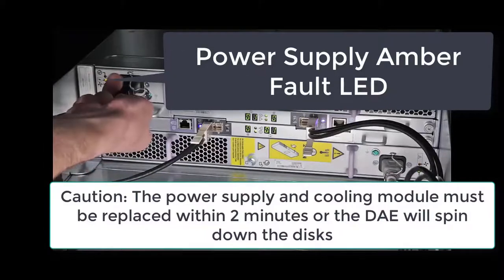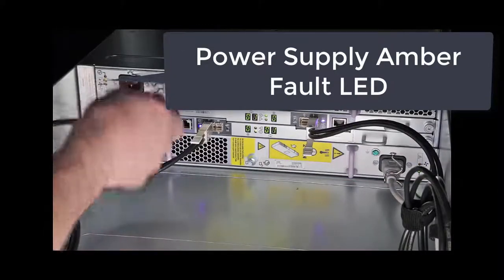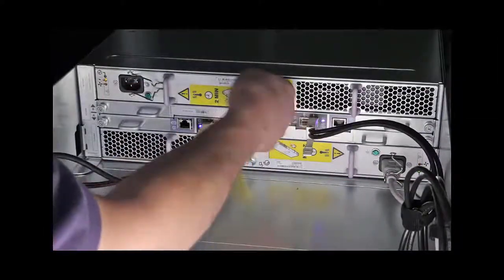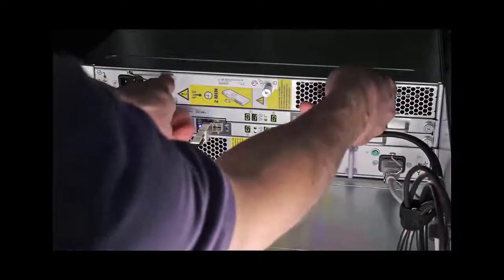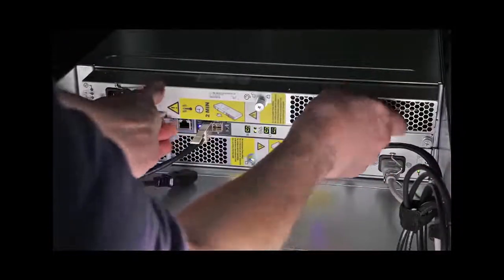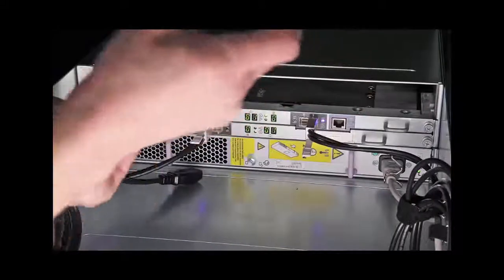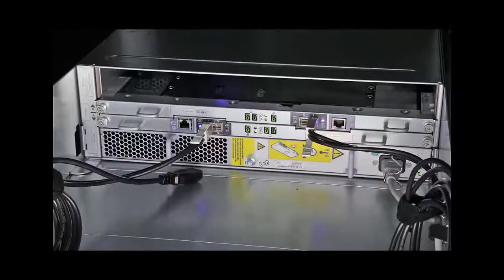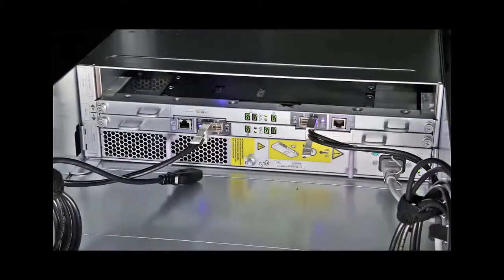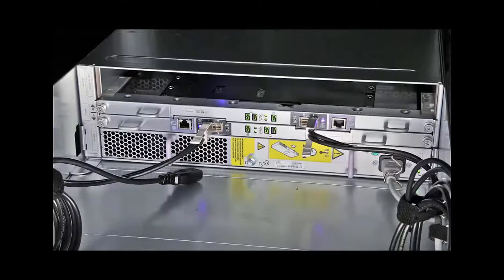You can go ahead and unplug the AC power. You're going to undo the captive screw with the screwdriver with your hand and pull the power supply straight out. You should have the replacement already handy. That should be the case in all your CRU replacements.